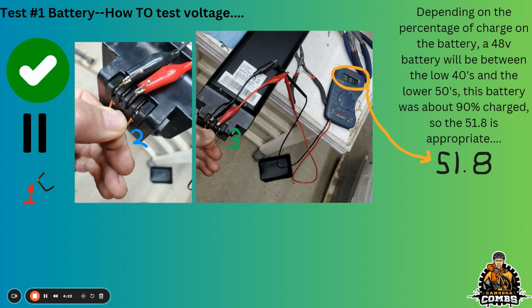Now, 51.8 is greater than 48 volts, but depending on the percentage of charge on the battery, a 48 volt battery will read between the low 40s and the low 50s. This battery was about 90% charged, so the 51.8 is an appropriate reading, and I would determine based on this test that the battery is not defective.